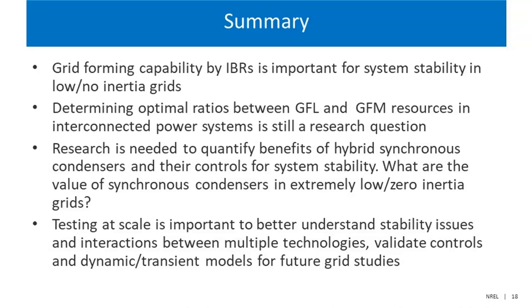Maybe it's a different phase of the same thing that Dennis just said. There's a lot of discussion in the industry about what the current rating of the grid-forming inverters should be, and it seems clear to some, myself included, that just throwing money at the current rating of the converters so that they can deliver, for example, as much short circuit current as a synchronous machine is uneconomic. But we need, as an industry, to have a good handle on the behavior of, and I think that was in the question, the saturation.